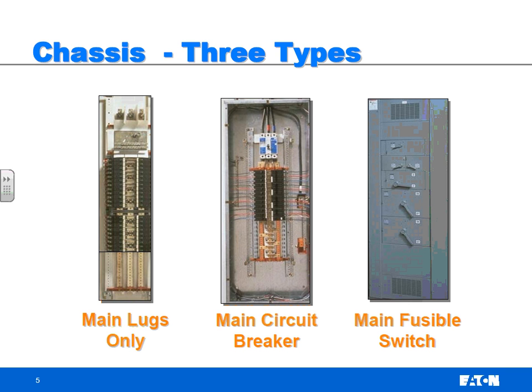And if you have main lugs only, what protects the chassis itself? If I've got 100 amp busing in this chassis, I've got all these 20 amp feeder breakers, but if I get a fault on this chassis itself, you don't have a main breaker to protect it. You go upstream to the switchboard breaker that feeds this, that actually is protecting that bus. Now, looking at this, which do you figure is the most cost-effective design? Main lug only or main breaker?